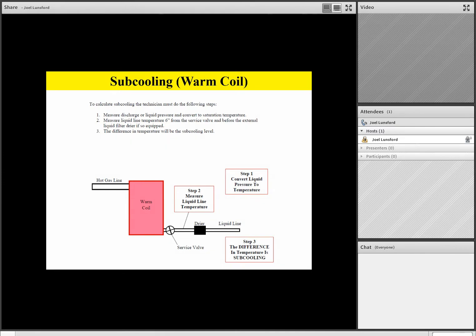There's only 3 conditions the warm coil can ever be in. Flooded, there's too much liquid in the coil. Starved, there's not enough liquid in the coil. Normal, a normal subcooling level will be about 10 to 15 degrees in the cooling mode. However, because of the physical size difference of the indoor and outdoor coil on a heat pump, the subcooling in the heating mode can go as high as 25 degrees because of the physical size difference.